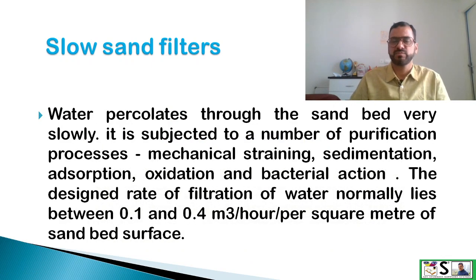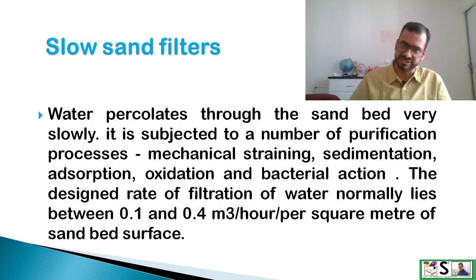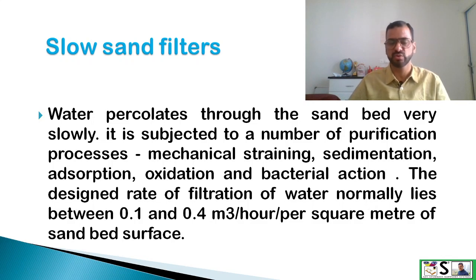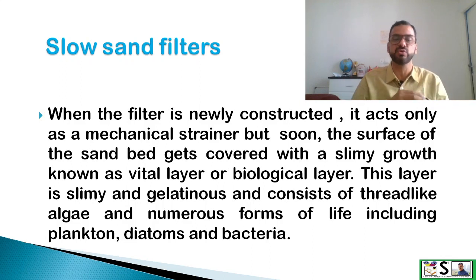Water percolates through the sand bed very slowly and is subjected to several purification processes: mechanical straining, sedimentation, absorption, oxidation, and bacterial action. The designated rate of filtration normally lies between 0.1 to 0.4 m³ per hour per square meter of sand bed surface. When the filter is newly constructed it acts only as a mechanical strainer.